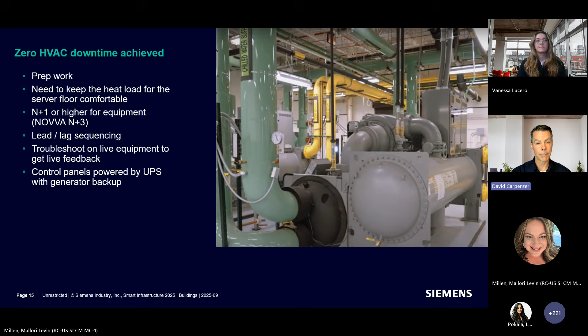So in redundancy, the number one thing that we need to address is, what does the customer need? And that is evolving. Legacy data centers that are now housing AI servers are needing to increase the density of their cooling, sometimes change the type of the cooling from a classic under the floor through the rack, or a hot aisle, cold aisle that they're running, to maybe a direct chip type cooling. That's changing how much cooling equipment is needing, changing thresholds of where PUEs are, etc. But that redundancy still has to exist.